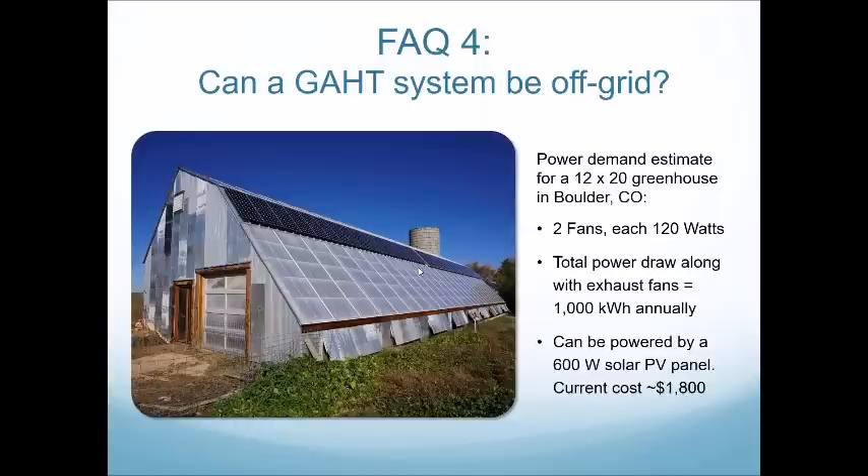Do you have any designs regarding the greenhouse sitting atop the GAHT system, or external GAHT systems? Yes — for someone with an existing greenhouse who can't get an excavator under it, we regularly design external GAHT systems using open land next to the greenhouse. The number one requirement is making sure you insulate around and above that system and also insulate the connections as they enter the greenhouse. The majority of our GAHT designs are below the greenhouse at four feet below grade, but external GAHTs do work.